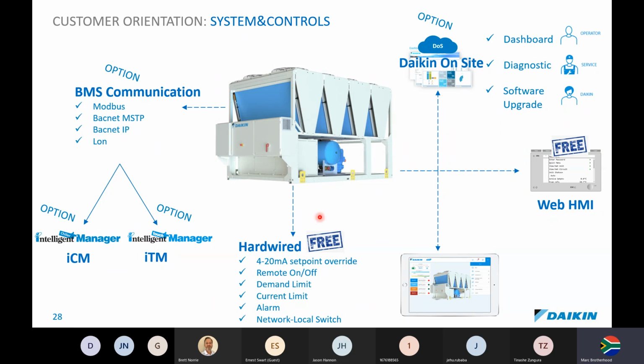And a lot of these things come free, hardwired, I should say. What's hardwired on the chiller is a 4 to 20 milliamp set point, demand limit, current limits, and network local switch, which didn't used to come free in the past. This now becomes part of the package with this model chiller.